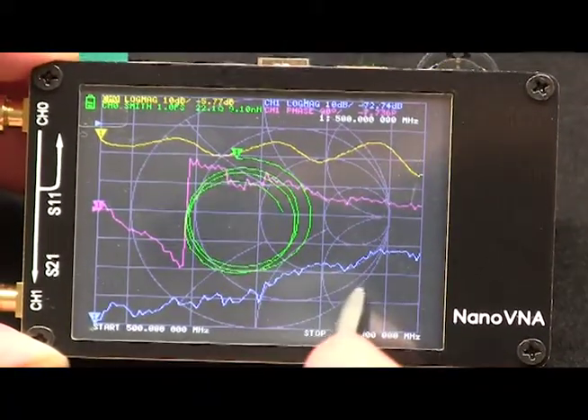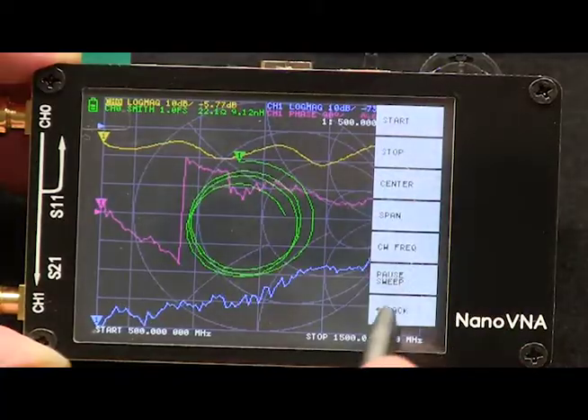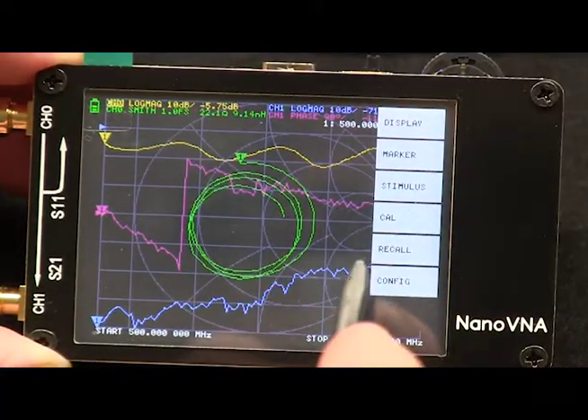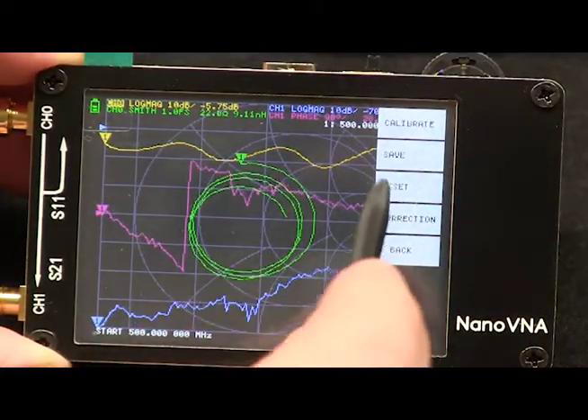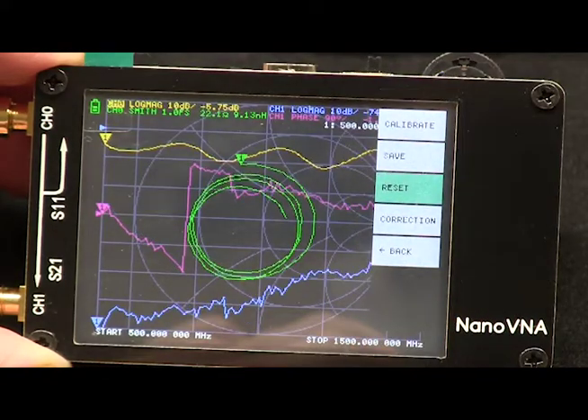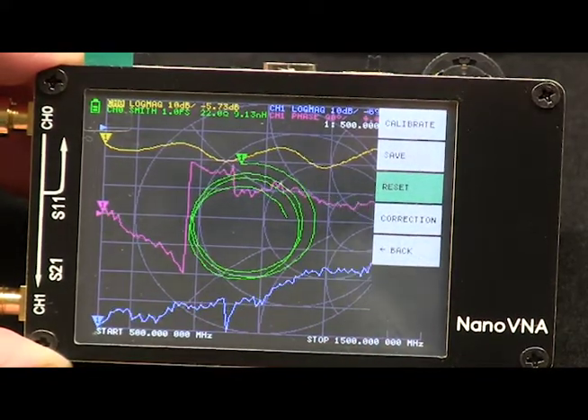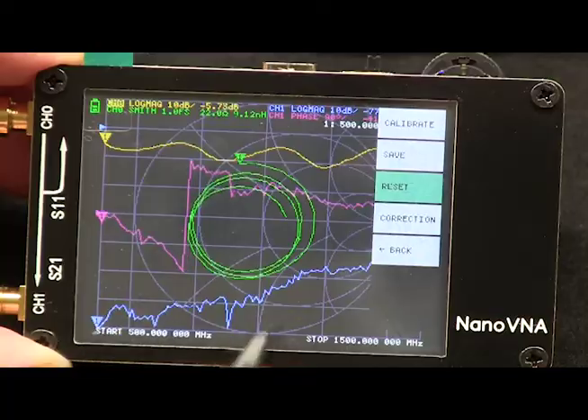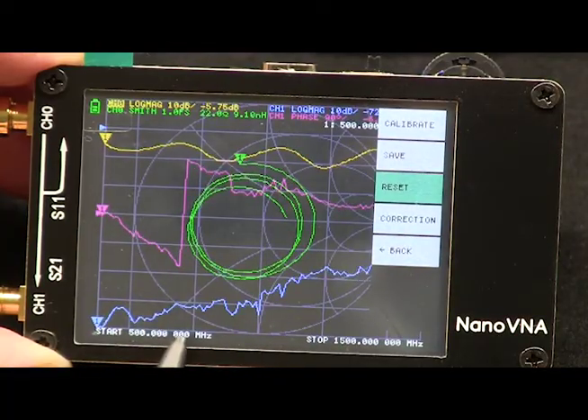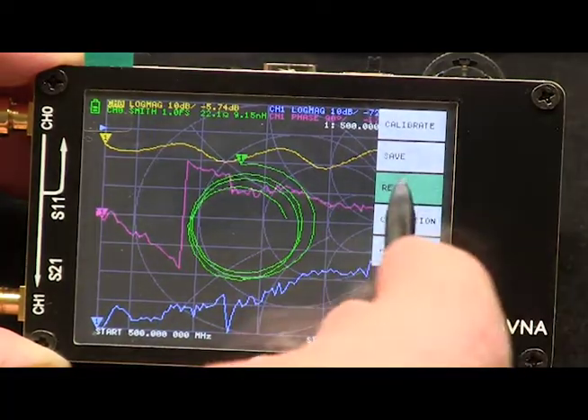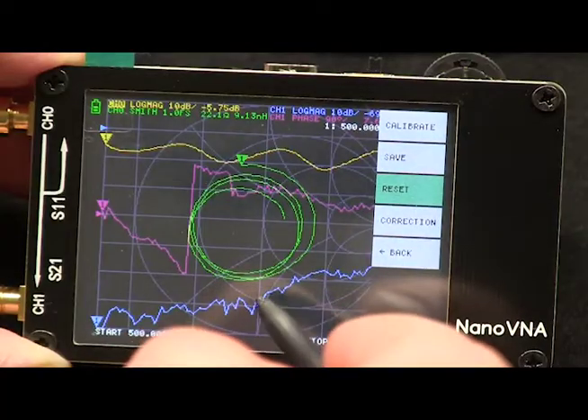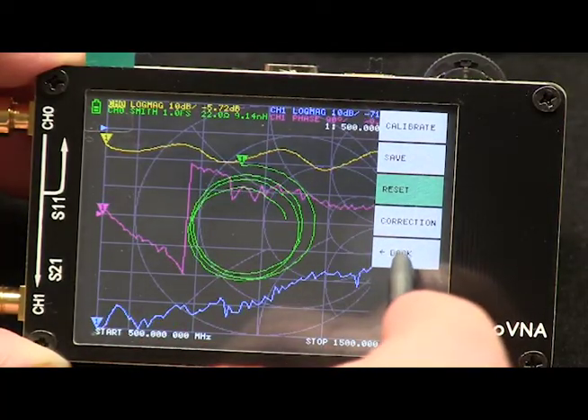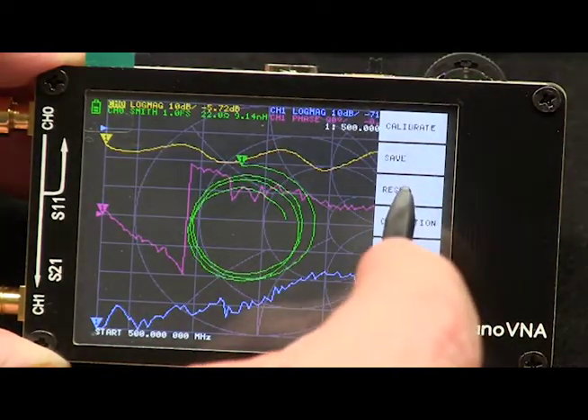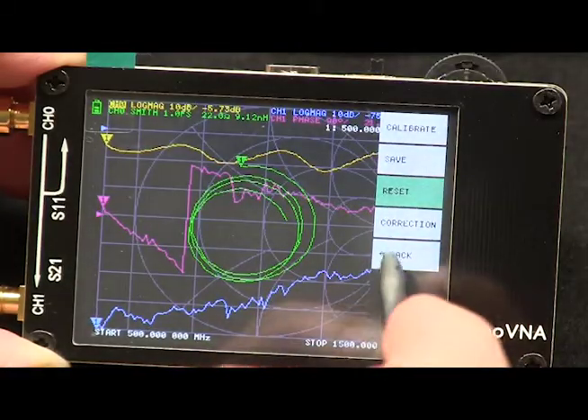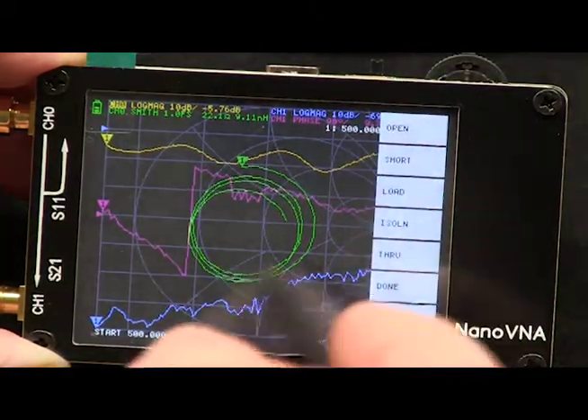Next, we're going to calibrate the device. Touch anywhere on the screen, hit back, and then we're going to go to cal. We'd like to reset everything. And you should do this every time you use the device because you may have changed some setting and you want the calibration to be reflective of your current settings. All right, so I'm going to go back again, cal. Let me just hit reset one more time. There we go. And now I'm going to go to calibrate.